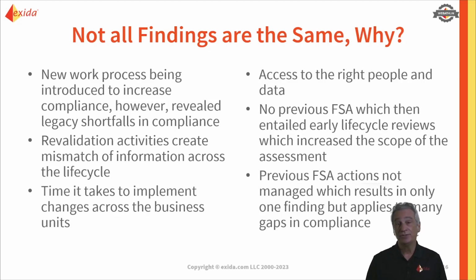And unfortunately that's true, because a lot of the times when I talk to companies and ask, have you done an FSA 1 or an FSA 2? They haven't done it. Some companies now are beginning to understand the benefits of doing this, because of course the purpose of a functional safety assessment is to help us find potential problems in that particular phase of the life cycle, especially systematic ones. So if we're not doing them, then we could be saving up a bunch of problems for later on when we have to do our mandatory FSA 3 before starting up. And of course, if we find problems there, that can delay startup and cause all sorts of other problems.